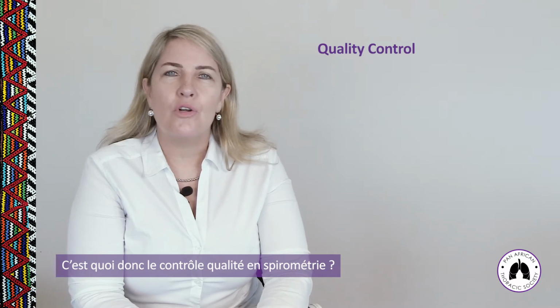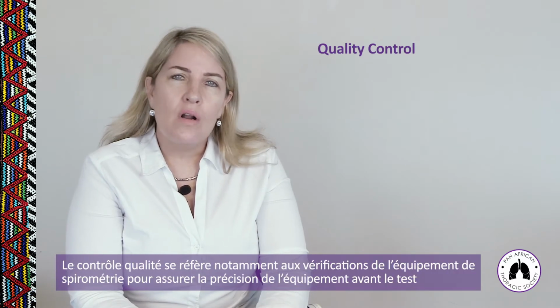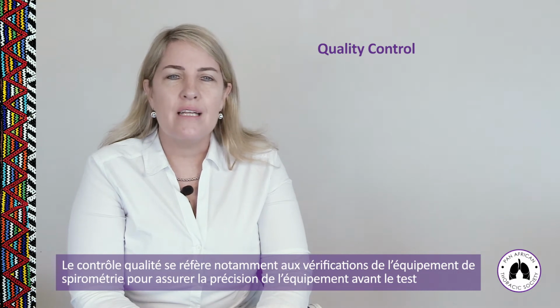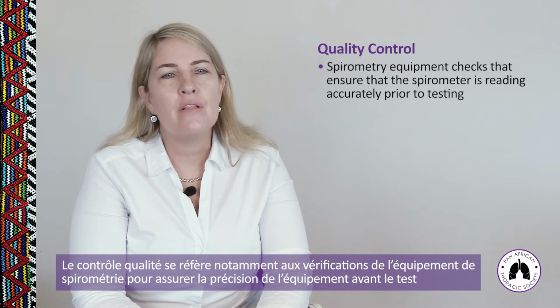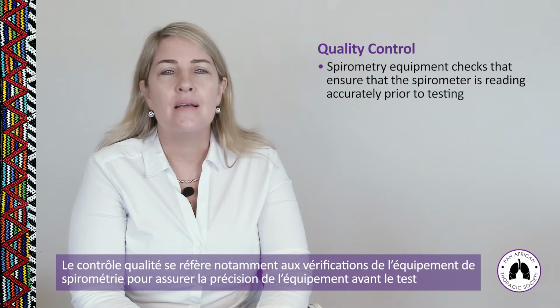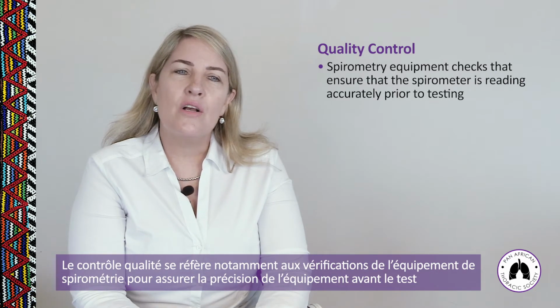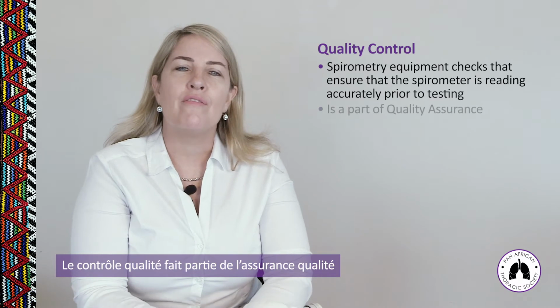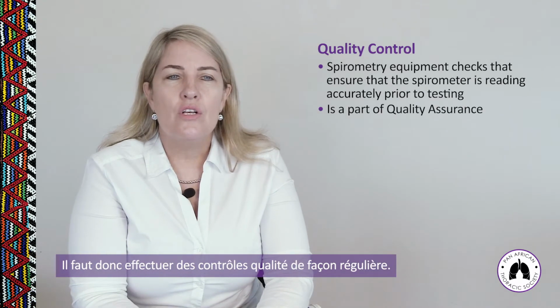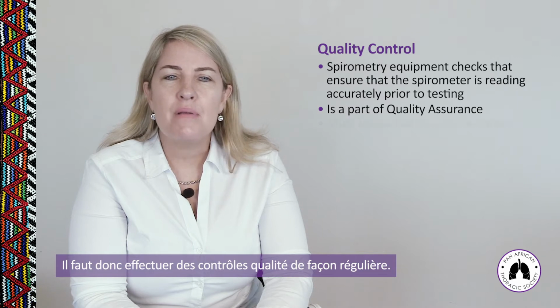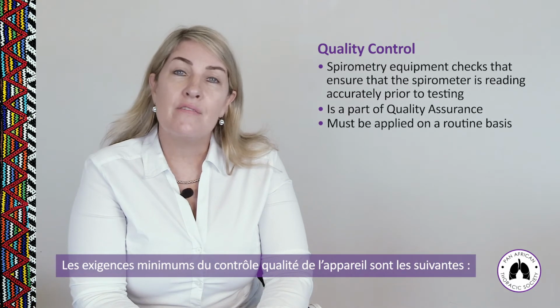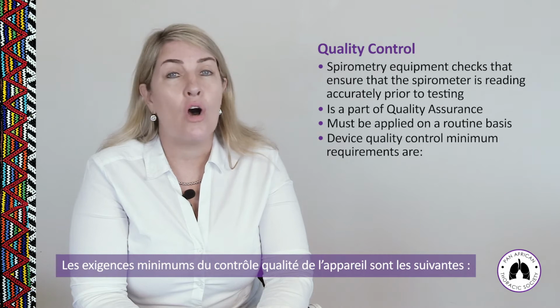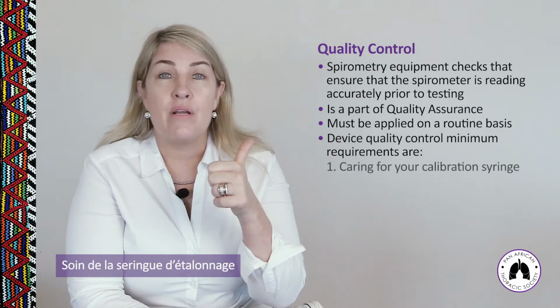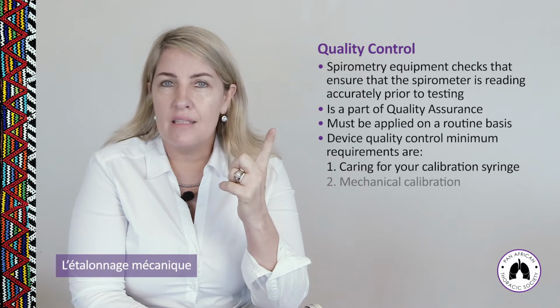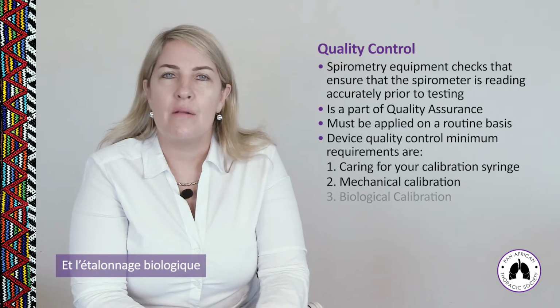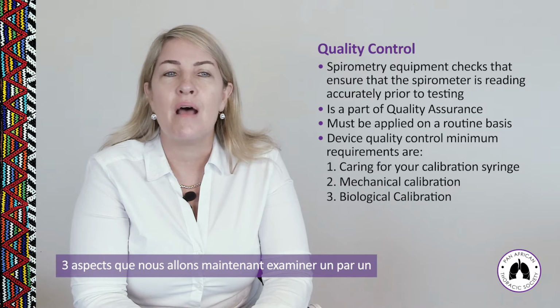So what is quality control then in spirometry? Quality control refers specifically to spirometry equipment checks that ensure that the spirometer is reading accurately prior to testing, and quality control is part of quality assurance. So quality control procedures must be applied on a routine basis. Device quality control minimum requirements are as follows: care of the calibration syringe, mechanical calibration, and biological calibration, those three things. And we're going to look at them now one by one.